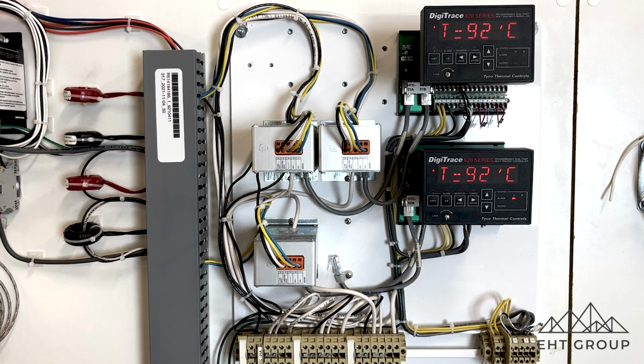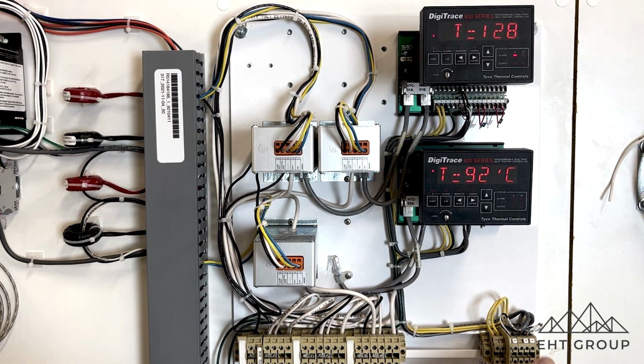So the 920 control panel's got a couple elements here. Obviously we've got our terminal blocks that have our incoming voltage and then our outgoing voltage for our heat trace circuits that are located in the field. Typically in a panel like this, you'll also have a set of terminal blocks that are for our DCS or common alarm wiring, and then also RS-485 communication wiring.